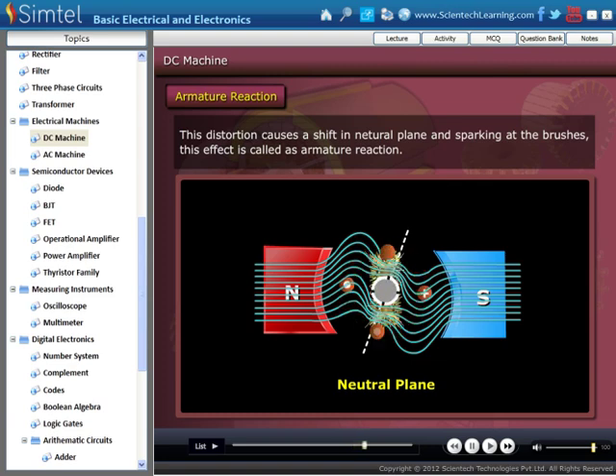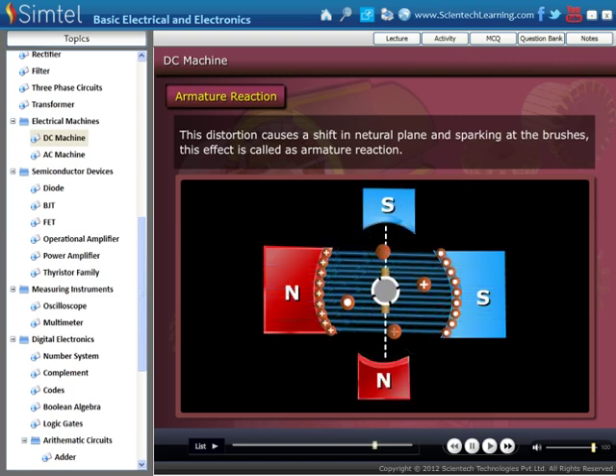There are two ways to maintain the neutral plane in its correct position. First by adjusting the brush position. The other way is by adding interpoles to the field. These interpoles are small magnets placed between the main magnets.